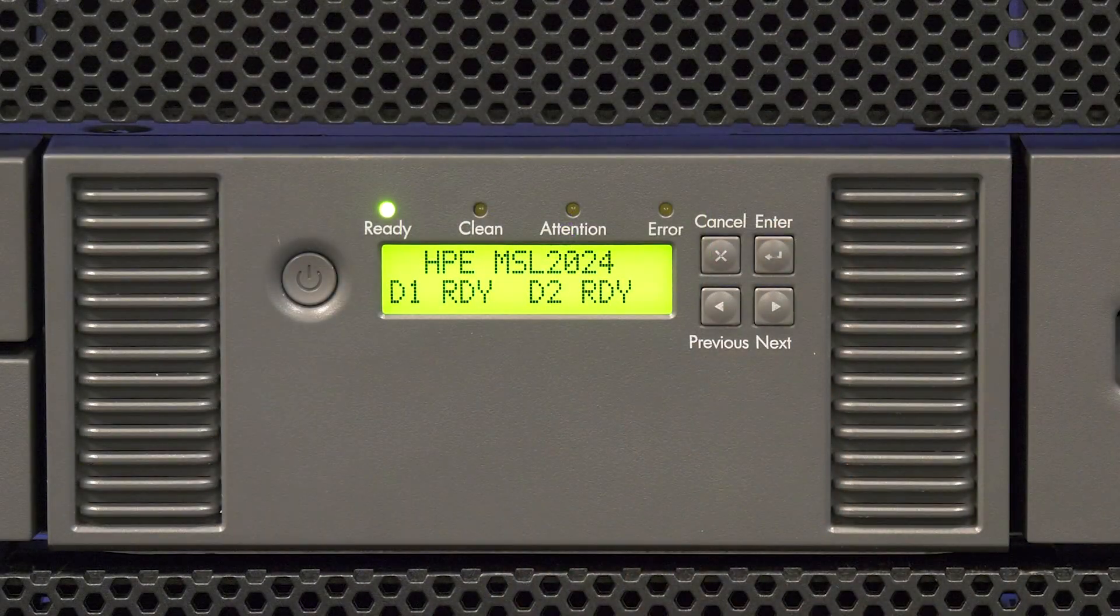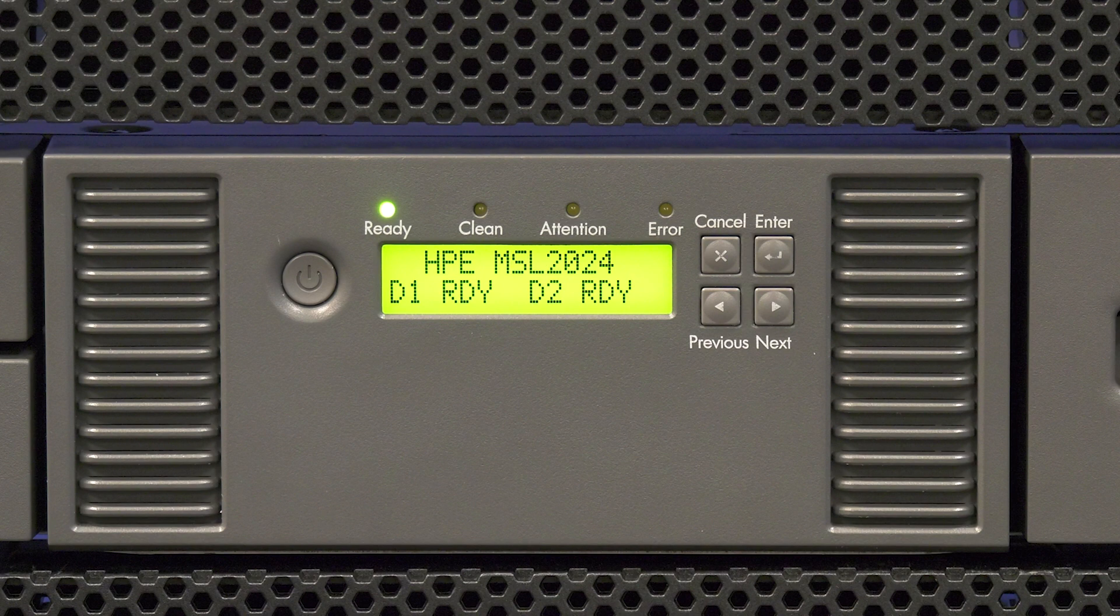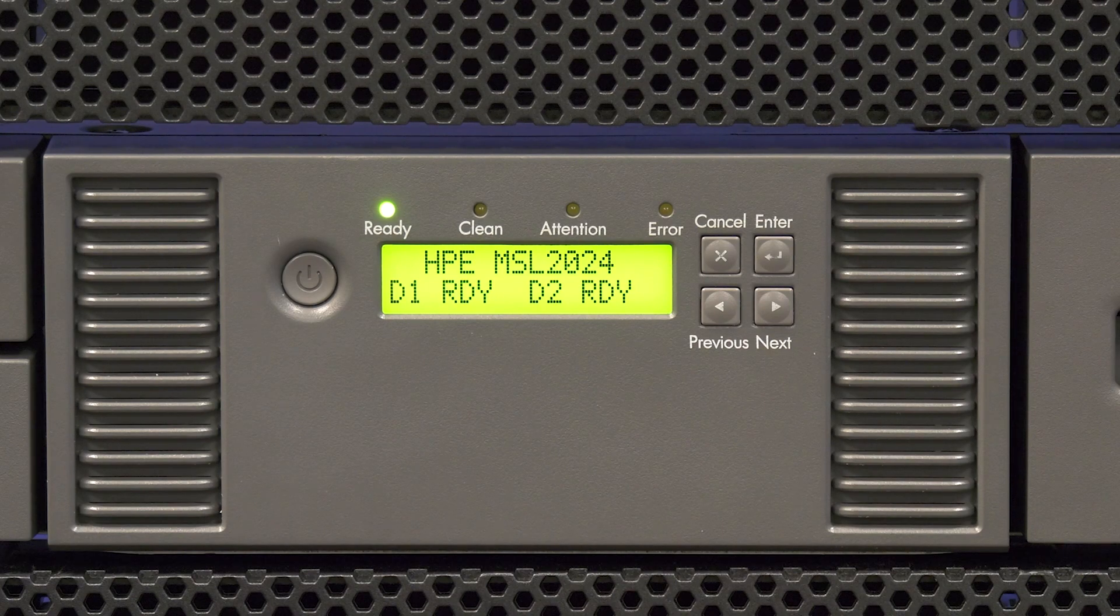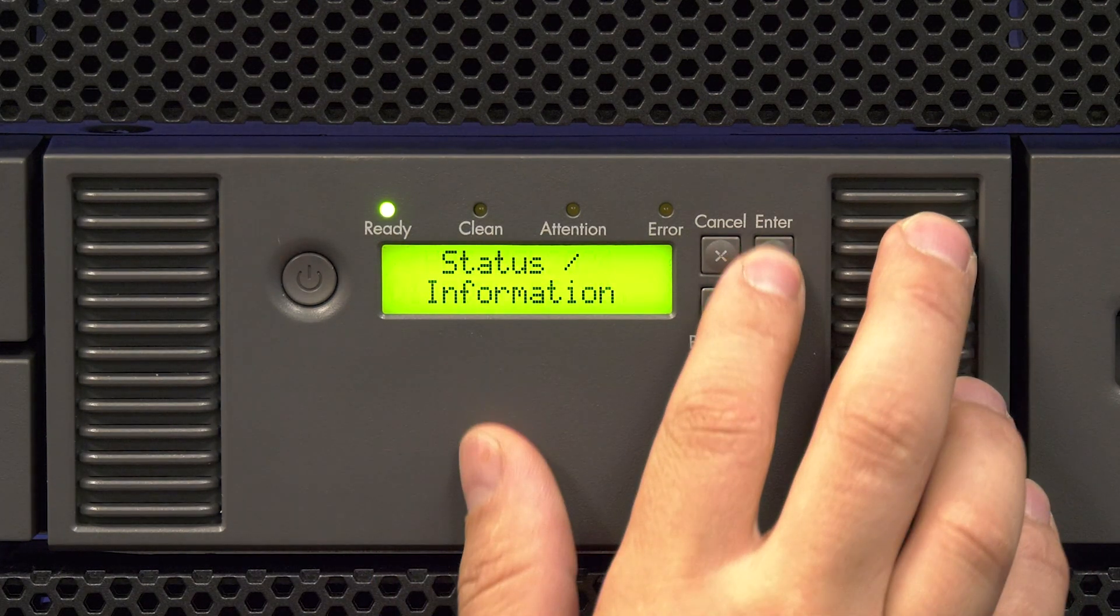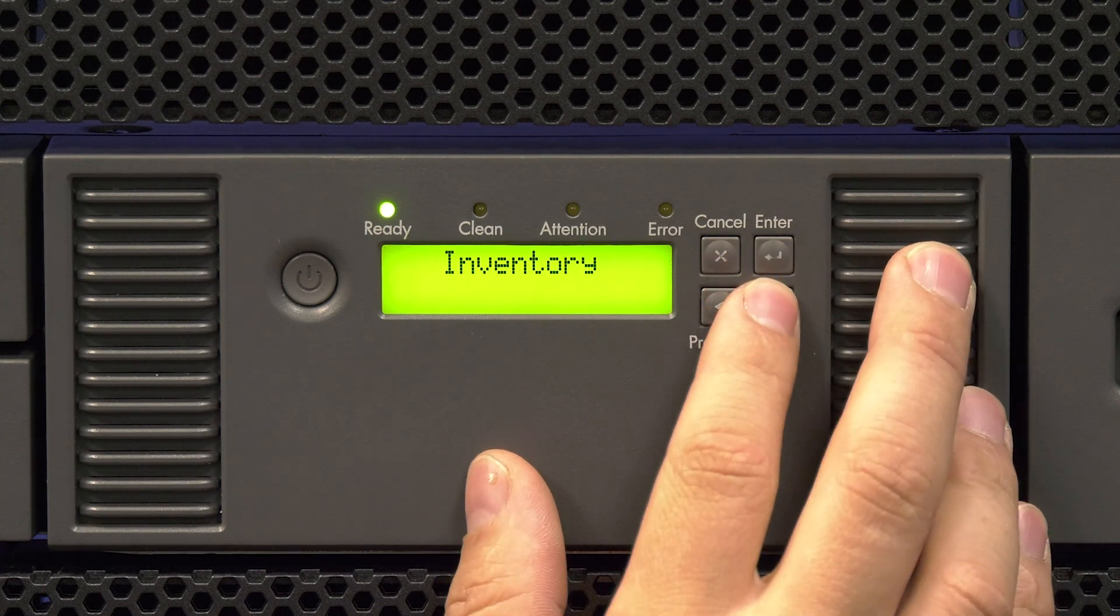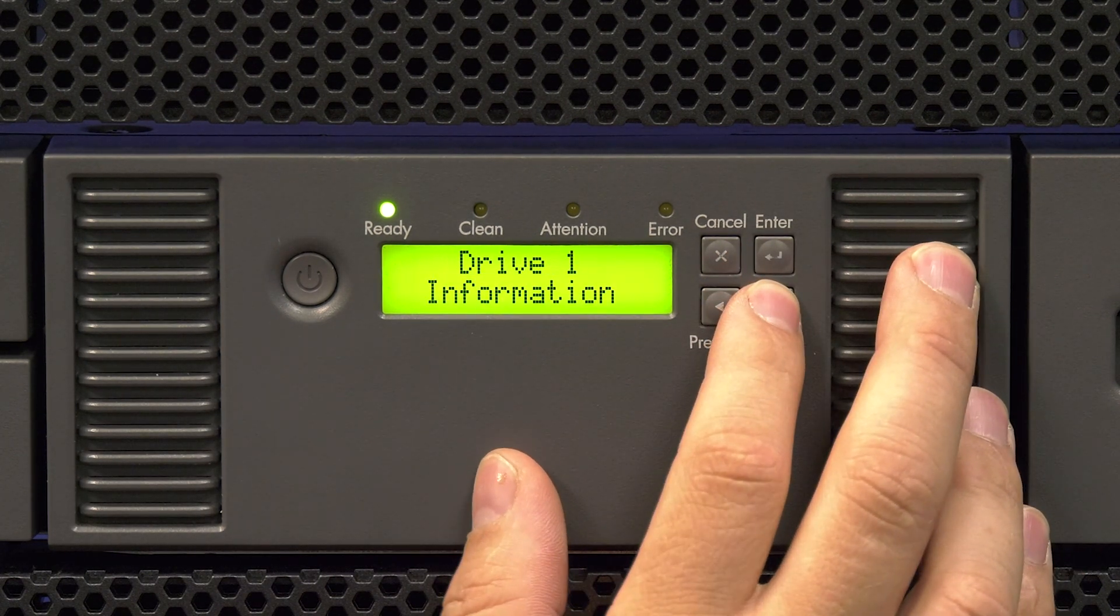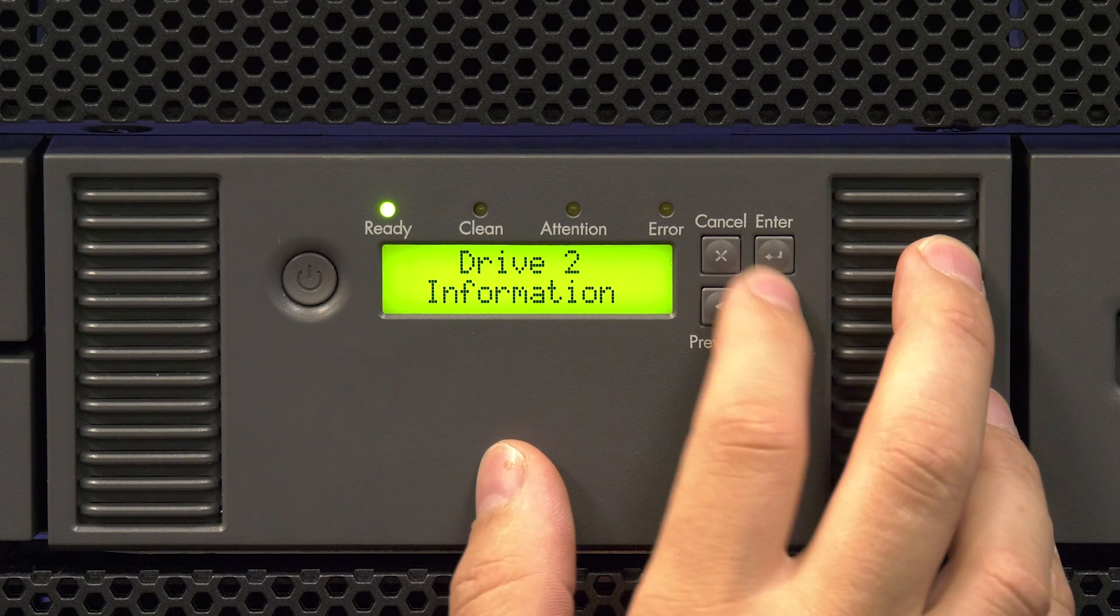If the drive you replaced has a fiber channel interface you will need to get the worldwide name of the replacement drive. To do this from the front panel hit the right arrow button until you get to the status/information menu and then hit enter. Then use the right arrow to scroll through the information options. You will see an option for drive 1 information and another for drive 2 information if you have a second drive installed.